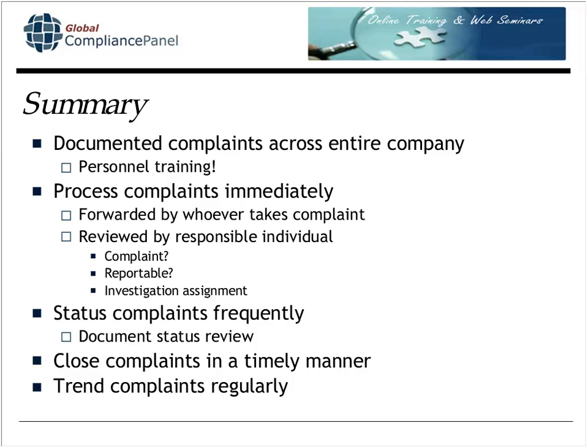Anecdotally, 30 days is a good goal. In practice, 60 days is a good maximum goal. If it were only up to your firm, you could do 30 days. But there are so many times where you need external companies involved. If an RMA has been issued, you have to wait for that. If your investigation determines that a particular component that you purchase is at fault and you issue a supplier corrective action request to the supplier of that component, you've got to wait some time. That's why 30 days might not be a reasonable goal.